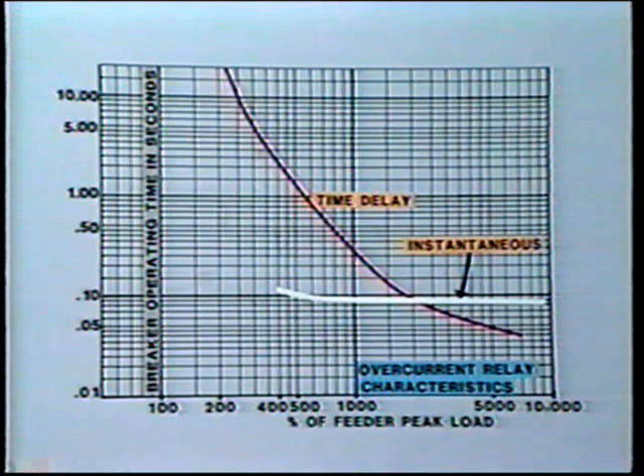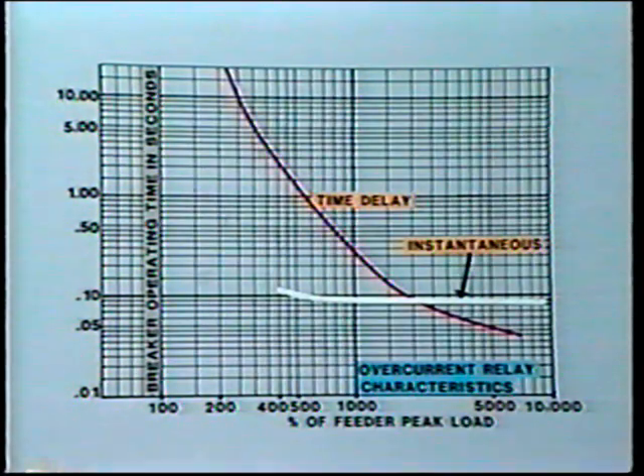The protective system must be able to measure and respond to its incoming signals in a very short time period. If the conditions are determined to be intolerable, then the protective system must take action immediately, usually to trip out circuit breakers. Conversely, if the fault is tolerable, then the protective system must not operate. In most power systems, the protective relays are rarely called upon to operate, but under fault conditions, it is absolutely imperative that they do operate precisely and provide the correct action.